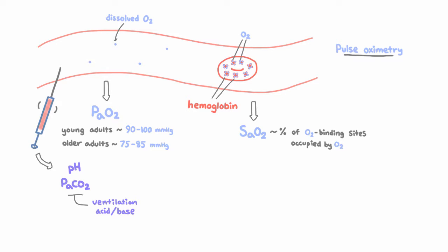The way that works is pretty complicated, but basically you shine light through the blood. It turns out that oxygenated and deoxygenated hemoglobin shine light back at different rates. So by measuring the reflectance, you can determine the percentage of oxygen saturation. This is great because it's totally non-invasive, and in most circumstances, it gives you a continuous evaluation of oxygenation.